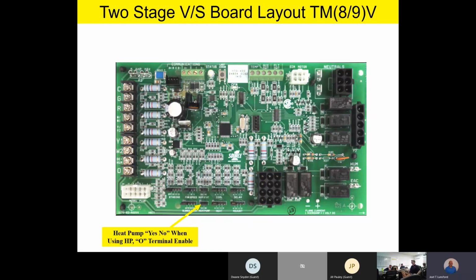If you have a dual fuel situation, if this furnace is set up with a heat pump, you can go ahead and configure it for a heat pump so that the board looks for the O terminal in the cooling mode. And again, if you have a straight AC unit outside, double check during your startup and commissioning that the jumper is in the no position on the heat pump. Otherwise, it'll throw a fault if it doesn't see anything hooked up to the O terminal.